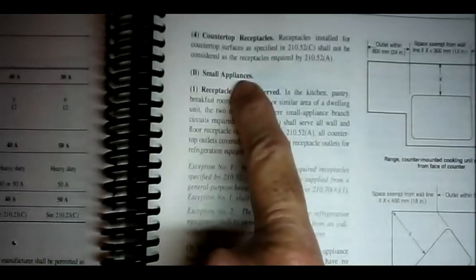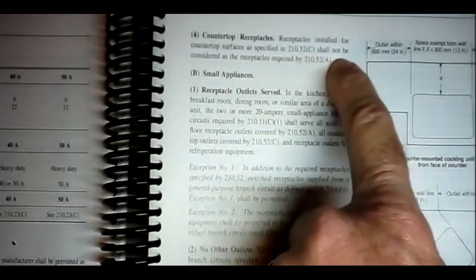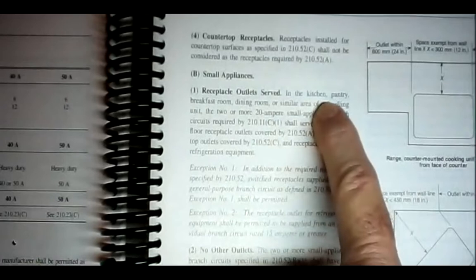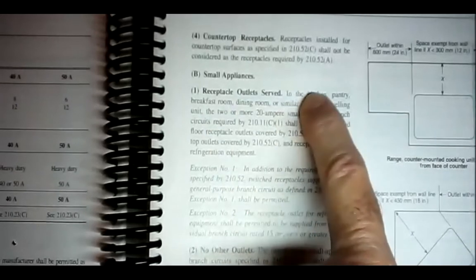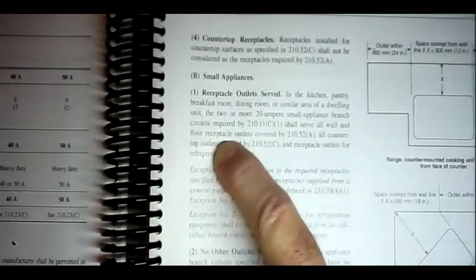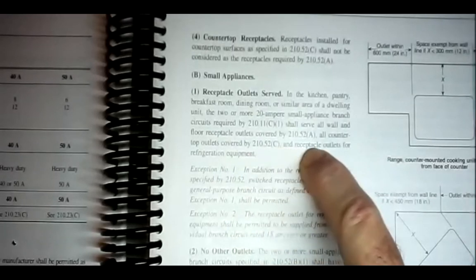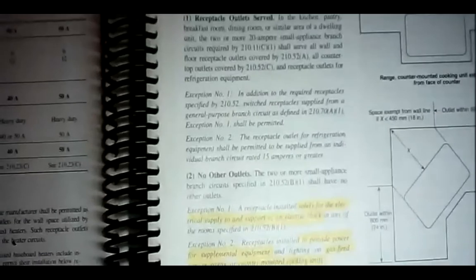Then we go on to kitchens. The kitchen is a little more stringent. Receptacle outlets for countertop surfaces as specified in 210.52C shall not be considered as the receptacles required by 210.52A. Receptacle outlets in the kitchen, pantry, breakfast room, dining room, or similar area — anything to do with cooking or eating — the two 20-amp small appliance branch circuits required by 210.11C1 shall serve all wall and floor receptacle outlets covered by 210.52A, all countertop outlets covered by 210.52C, and receptacle outlets for refrigeration equipment.